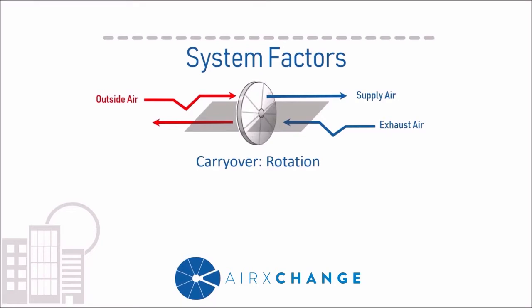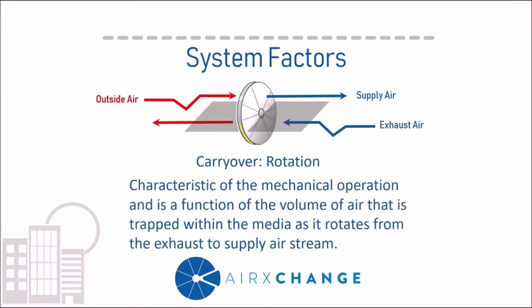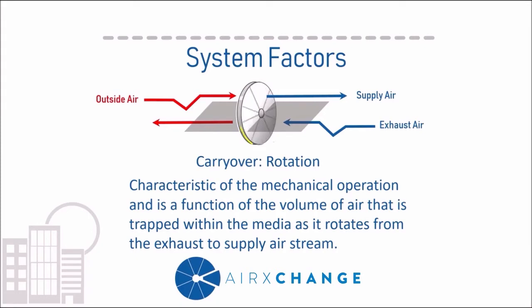Carryover is a function of mechanical operation. As the wheel rotates between the air streams, there is a certain volume of air trapped within the media. When it rotates from the exhaust stream to the supply stream, that volume of air gets deposited into the leaving air stream. Therefore, carryover is primarily a function of rotational speed and the geometry of the wheel. When you combine carryover and leakage together, they form the driving mechanism that impacts EATR.